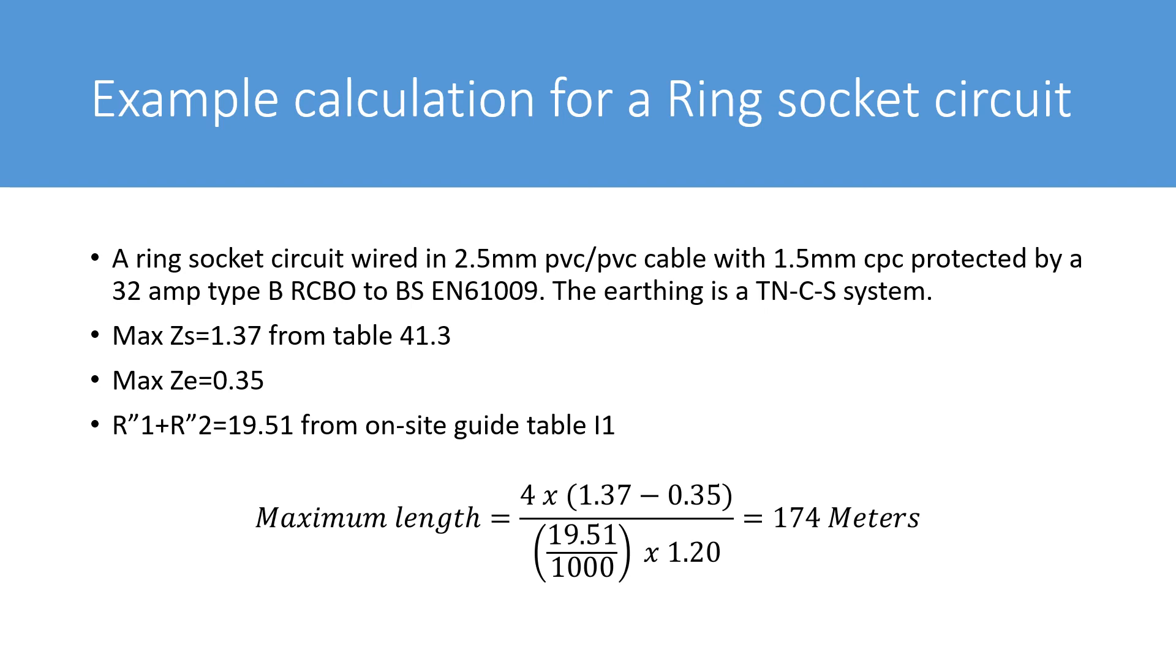So here we have the equation below and the equation is the same except for the fact that we have this multiplier of 4 to account for the fact that it's a ring circuit. So if we do that equation that comes to 174 meters.